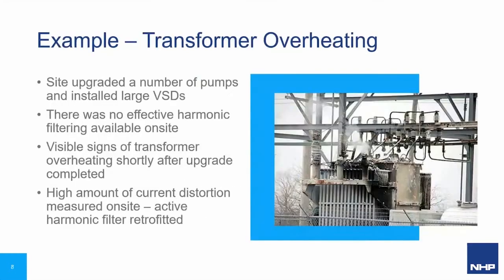Here's an example of a site that has harmonics present. They upgraded a number of pumps on site and installed a couple of large VSDs. At the time, there was no effective harmonic filtering available on site, and as a result, not long after the VSDs were powered up, they started seeing some visible signs of the transformer overheating. Power quality analysis was done for the site, and a high amount of current distortion was measured. So the best result was to get an active harmonic filter in there.